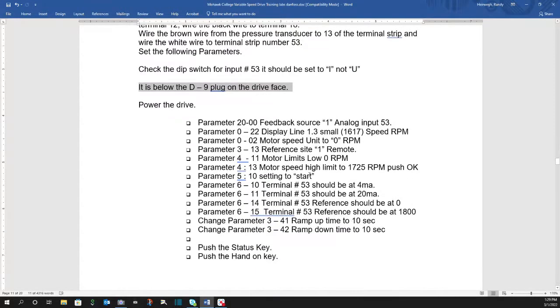And here are all my parameters. Feedback source, which we did before, was an analog into number 53, 20-0. And again, it's already completed. I've done all these things. The small line on the display LCP to be RPM. And then we have to go into the motor speed units. We're going to change it to RPM as well. So these are all pretty much standard, easy things to do, and we've done them already in my other videos.